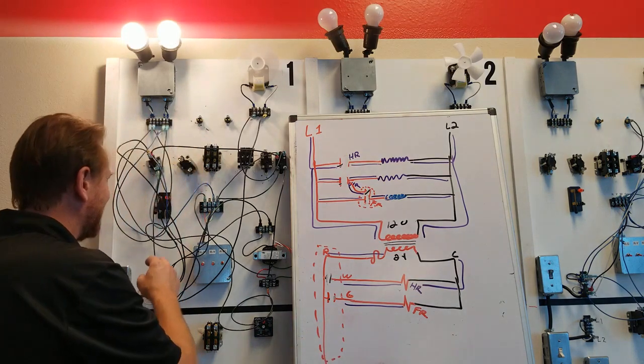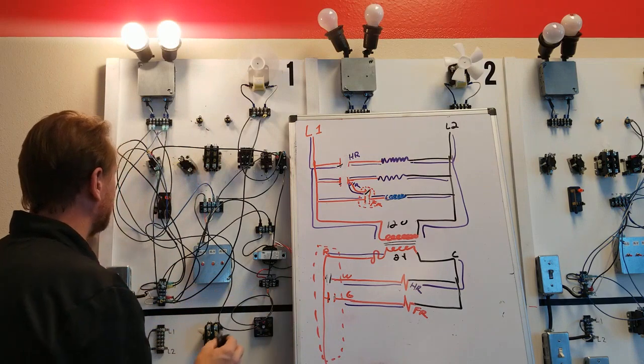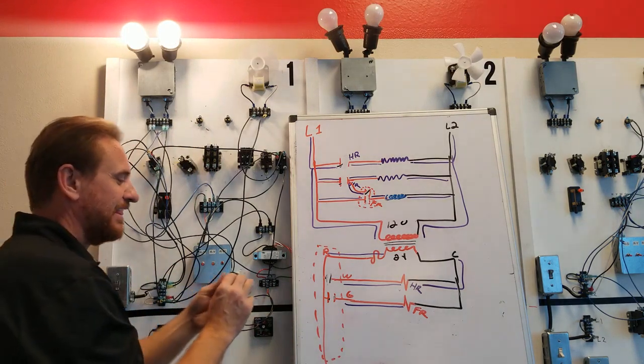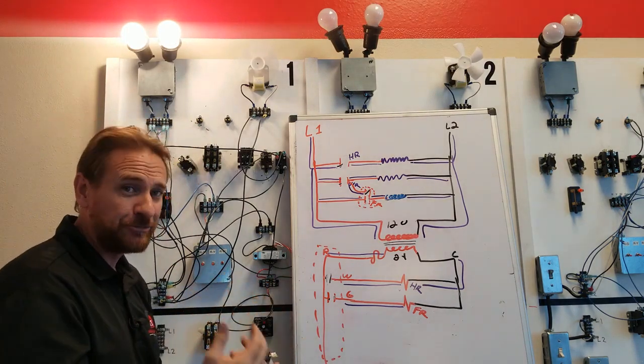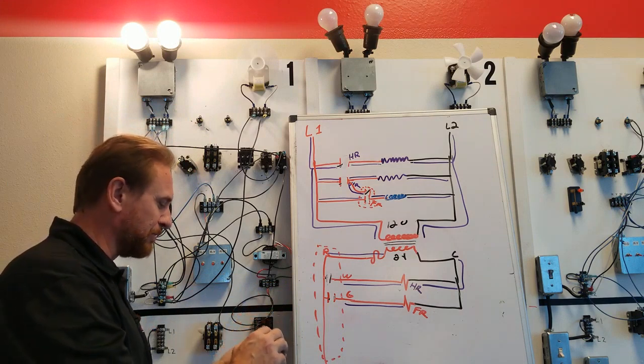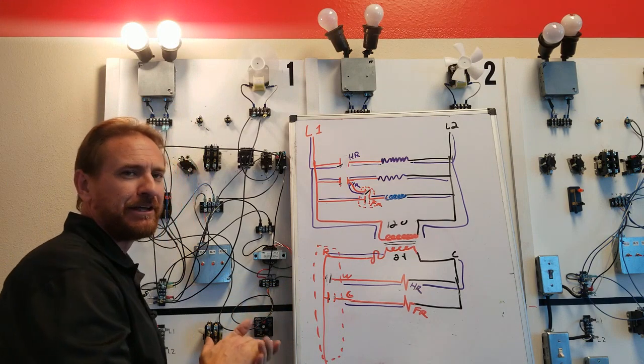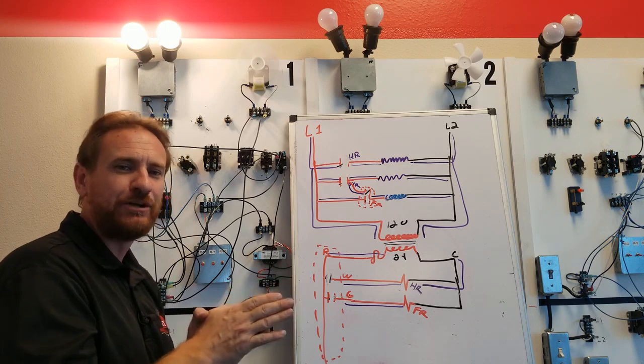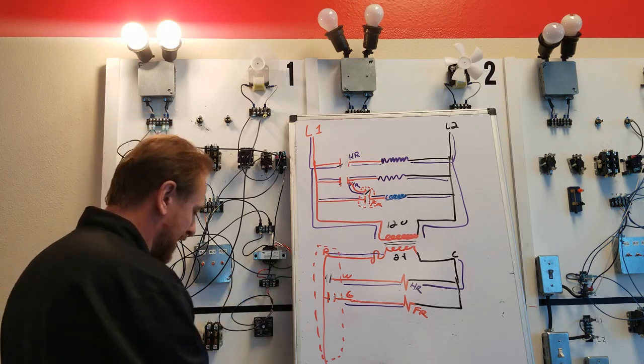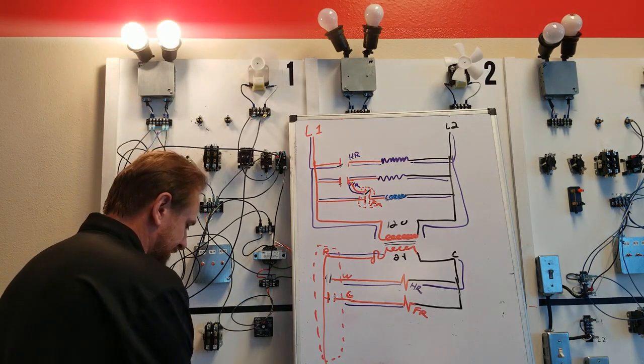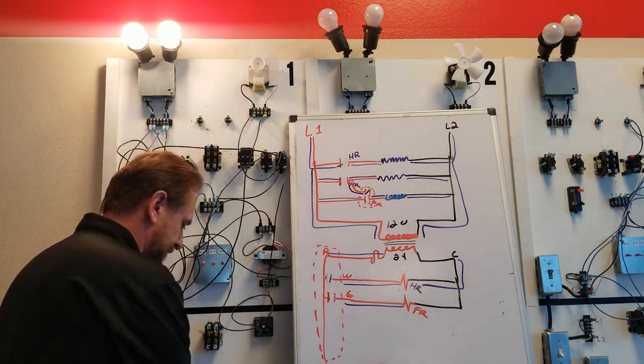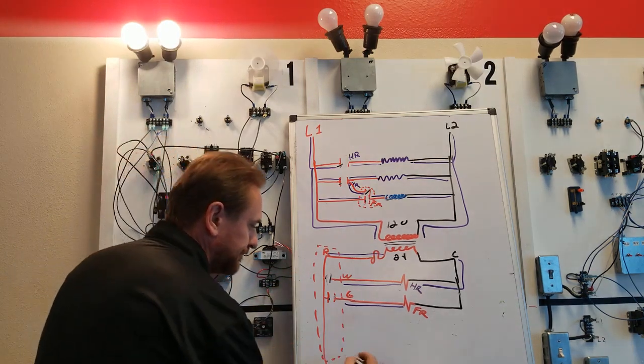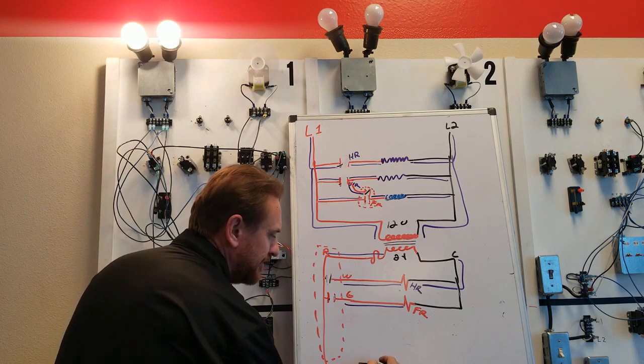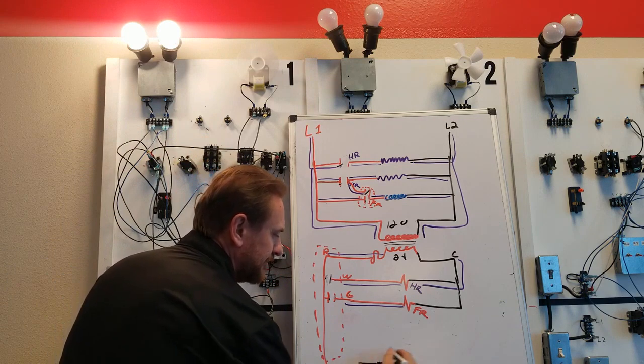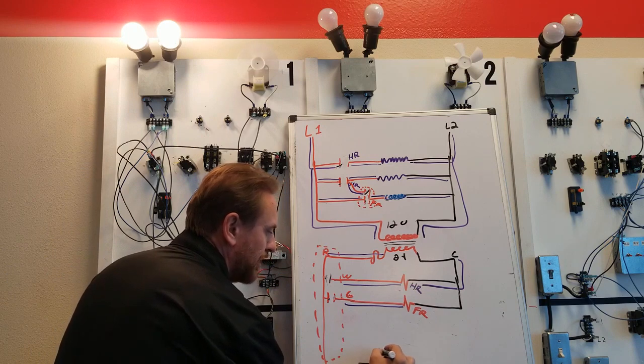What's great about that is if you touch this, you'll feel a burn. We put 24 volts in this. This gets warm, but it doesn't get warm immediately. It takes a little bit of time. So it starts getting warm, and what that does is it warms up that bimetal. Now, bimetal is two dissimilar metals. When heated, it warps. That bimetal will pop. When that bimetal pops, it causes these switches to close. And if we were to draw it out, we would have a resistant heater here. We would have a bimetal. We would have then two rods that come up.